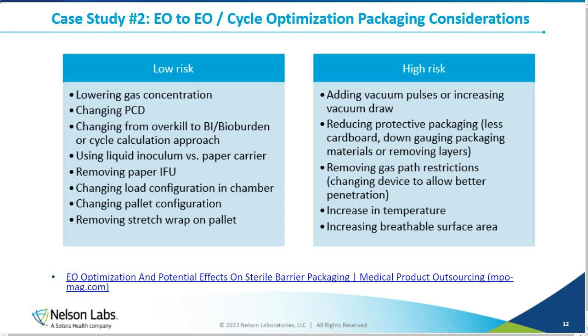When you reduce your protective packaging, either by pulling out some of the cardboard, or maybe you use thinner materials or remove extra layers in your protective packaging, this is going to make sterilization easier, but that's less protection for your sterile barrier system. And so you'll need to assess whether it needs that extra protection or if removing that would be okay.